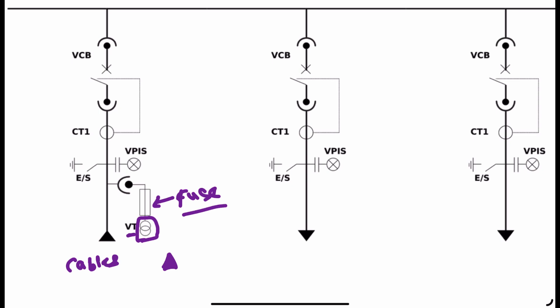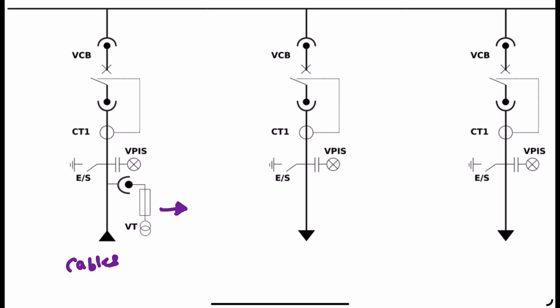This is the symbol of the voltage transformer, and on top of the rectangle you can see a fuse — so it is a fuse-protected voltage transformer. This particular bracket symbol indicates that this voltage transformer is a withdrawable type, meaning if necessary I can completely remove this voltage transformer from the panel. If it were a fixed type, it would have a simple connection without the bracket symbol.